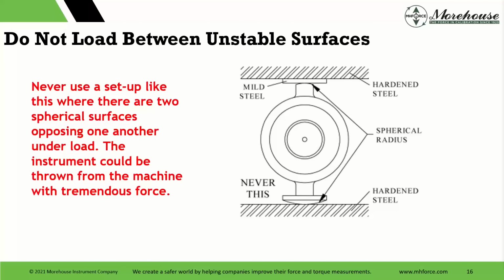Under load, the instrument could be ejected from the machine with tremendous force. Never use a setup where there are two spherical surfaces opposing another without making the appropriate adapters to contain the instrument. We have developed special adapters for this type of loading. Without the appropriate adapters, the instrument could be ejected from the machine with high force. That's what we're showing here.